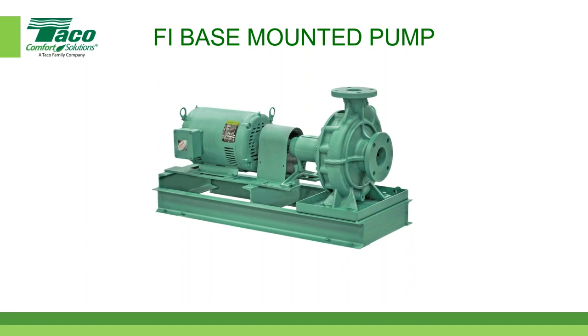But here's a picture of one. And all we're going to say is a base-mounted pump is mounted on a base. Pretty straightforward, right? So let's look at the components that make up the pump. One of the major components, as you can only believe, is the casing or the wet end or the volute. And that's where all the magic happens, right? That's where the water gets brought in, circulates around by the impeller, and then gets distributed. You'll hear different terminologies, but there's the casing, wet end, or the volute.